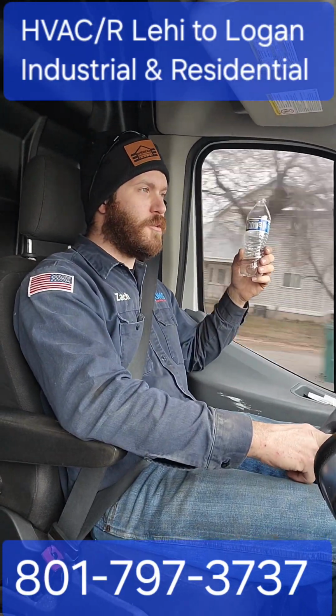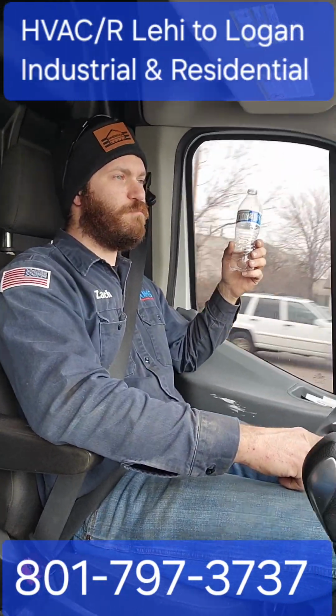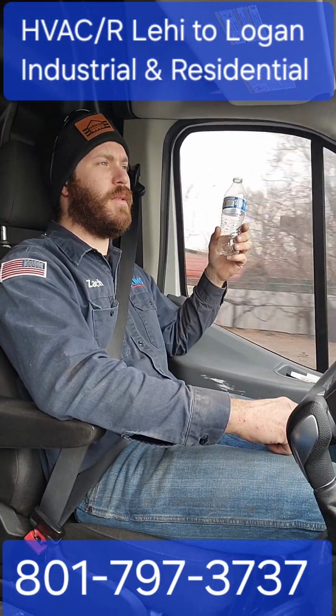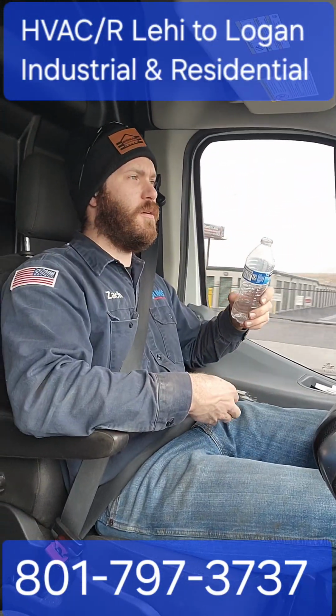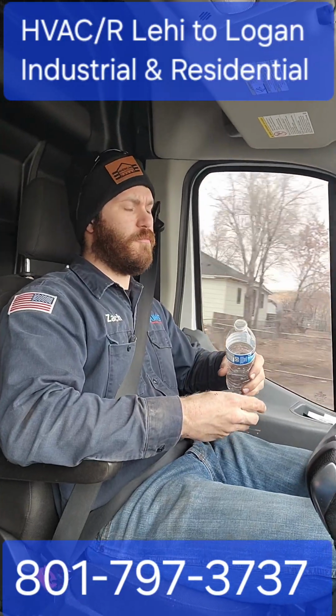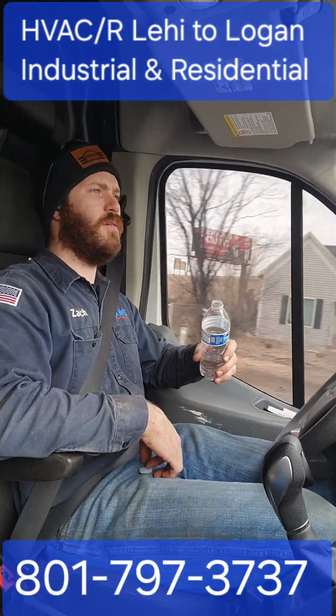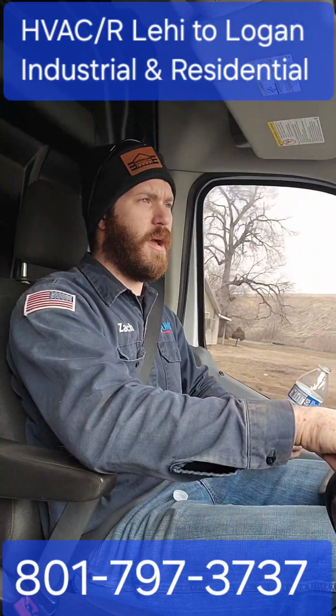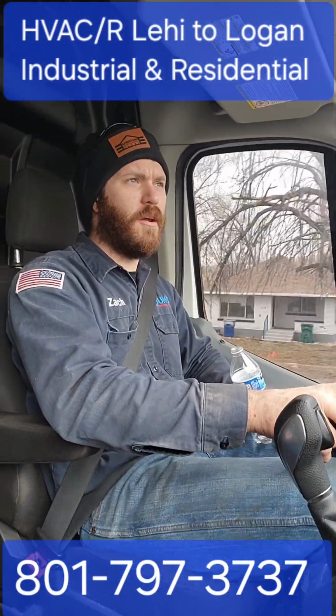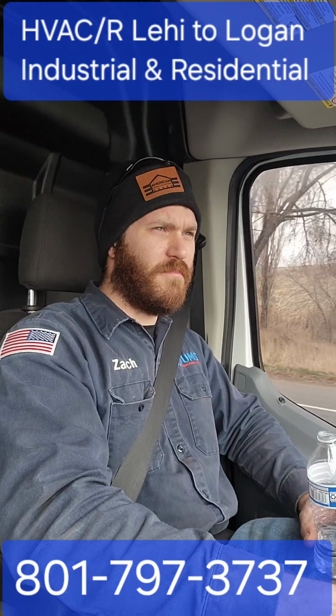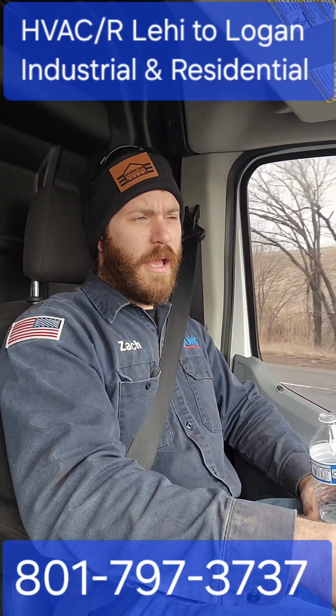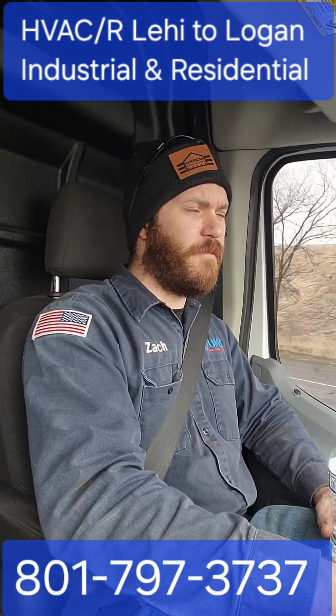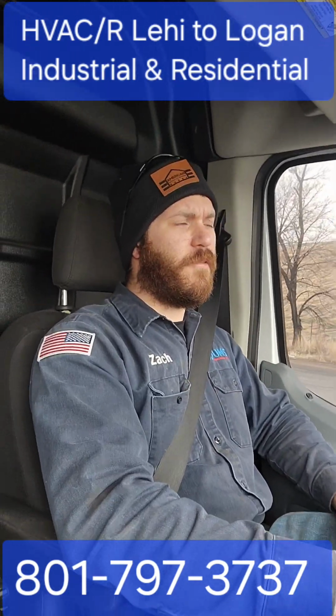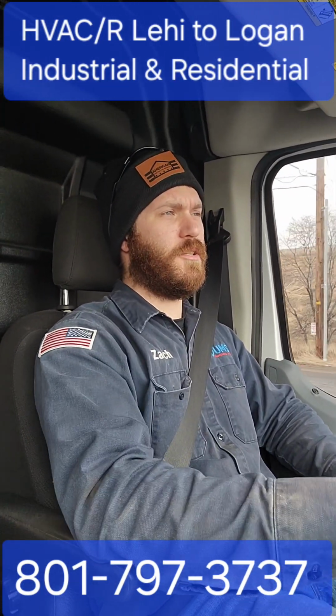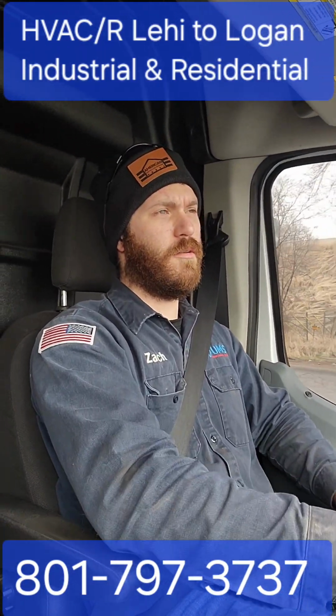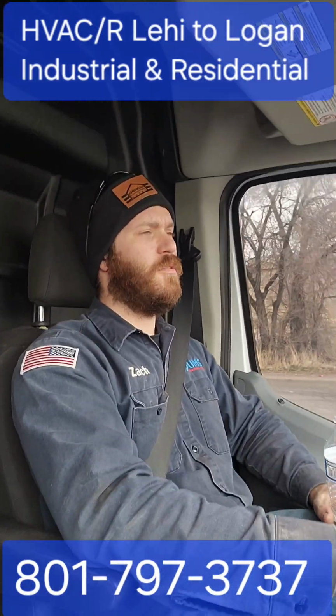Okay, so this house that we're going to had a complaint that the furnace was intermittently not heating. It would heat, and then it would just shut off all night, and they would reset it, and then it would kick back on. But it would only not do it sometimes. And I go there, kick the furnace on, it fires right up. So I reset it a few times and finally get it to fail. And the furnace gives me an error code for the pressure switch, either not closing or reopening after it's closed.